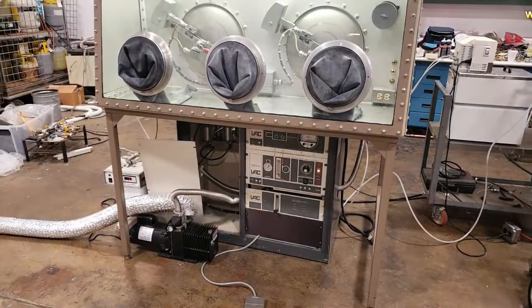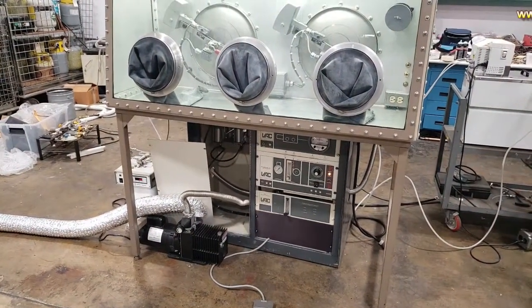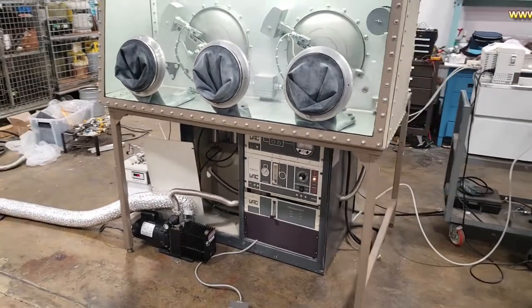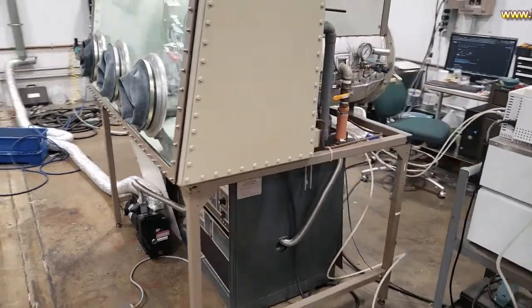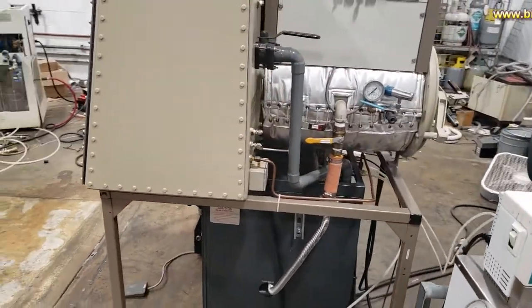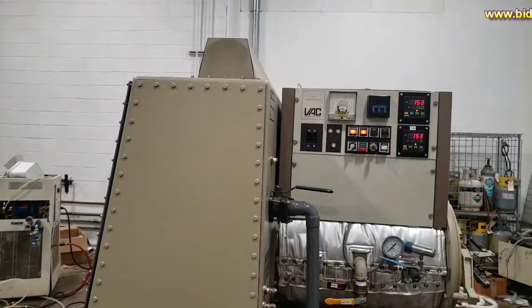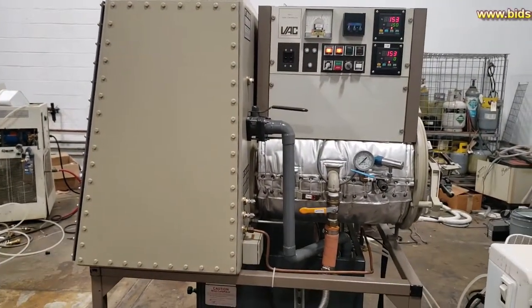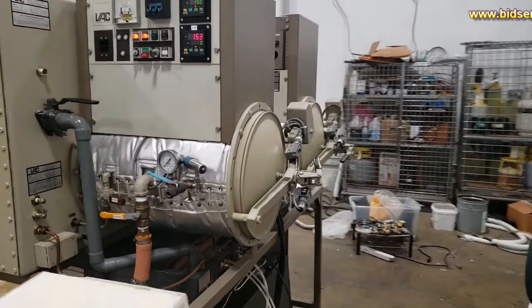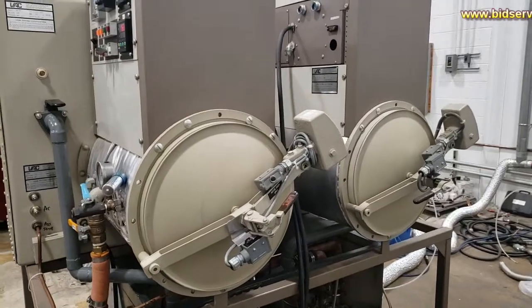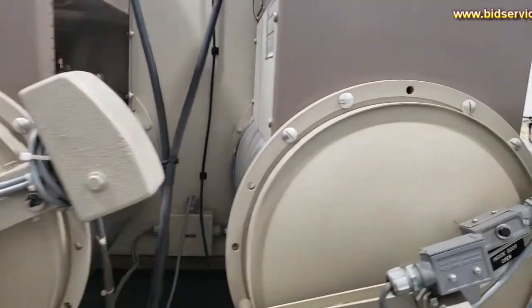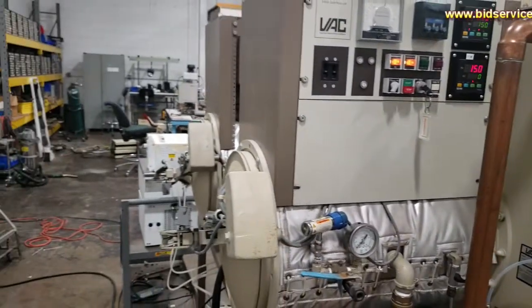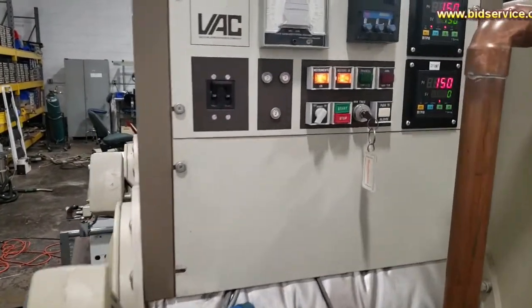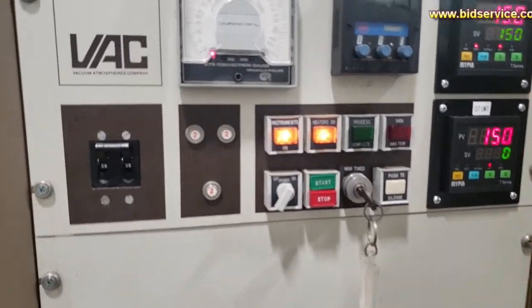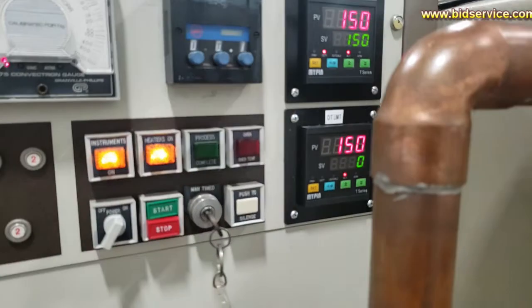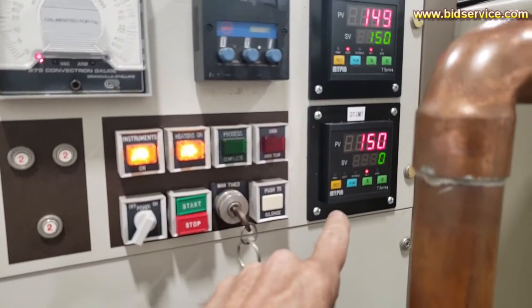Okay, this is our video demonstration of the VAC HE43 glove box. Take a walk around it first. As you can see, there's two antechambers that are heated. So there's heaters inside the antechamber. Got one on either side here. As you can see, I'm running them at 150 Celsius using a temperature controller. And here's our limit. That's for over temperature protection.